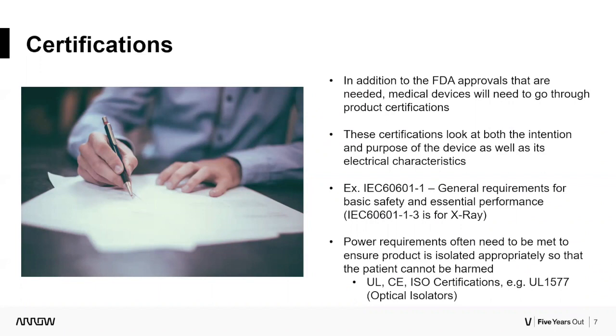If there's a power requirement associated with these, particularly if you're looking at anything that's going to interact with the body electrically, these often will carry isolation standards with that. The big reason is that if you have electricity interacting with the human body, there are some really bad interactions that could happen from burning and too much current passing through the body. So there are some really key things needed from isolators.